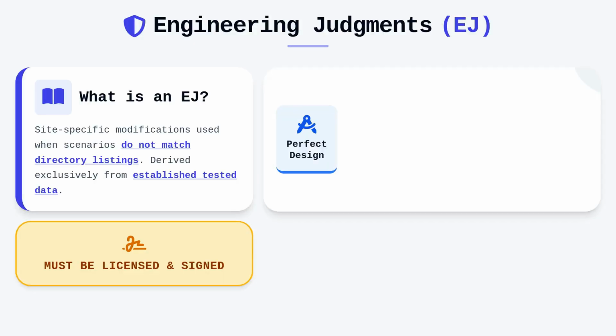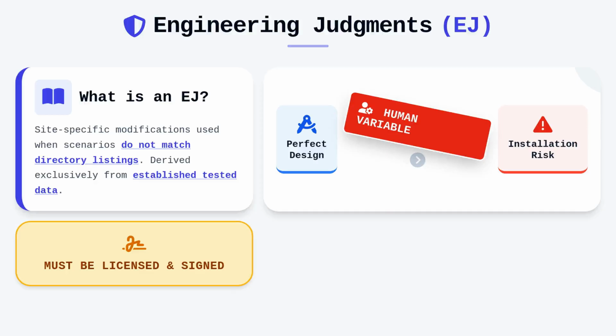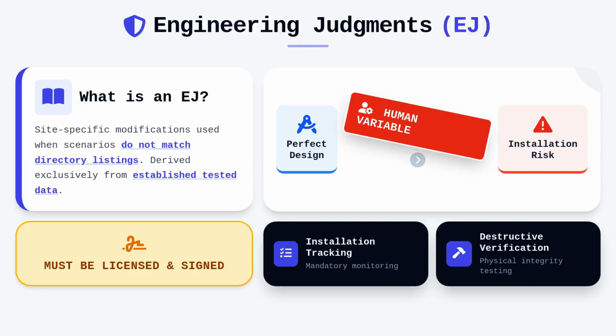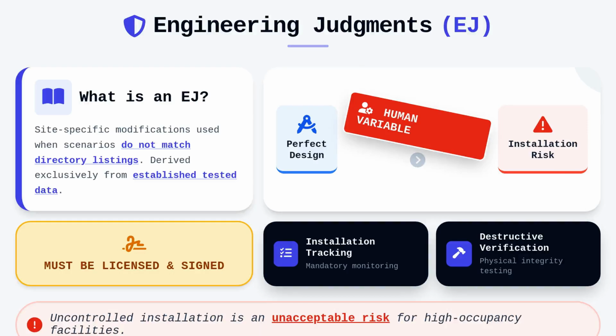Even with the perfect design and the most appropriate materials, the human element remains the greatest variable. We must account for installation tracking and mandate destructive verification in our quality assurance programs. Without these controls, the barrier's integrity relies entirely on the technician's accuracy, which is rarely an acceptable risk level for a high occupancy facility.